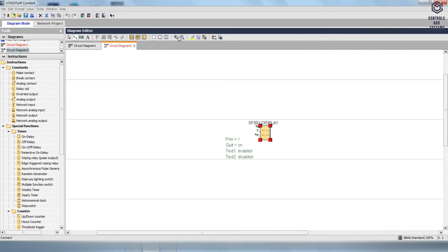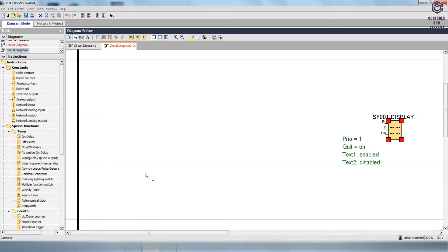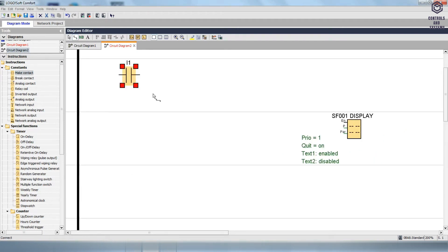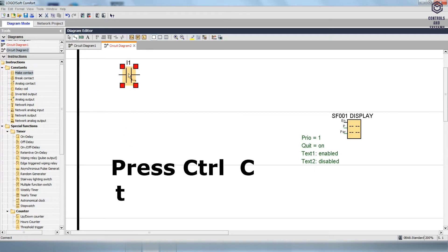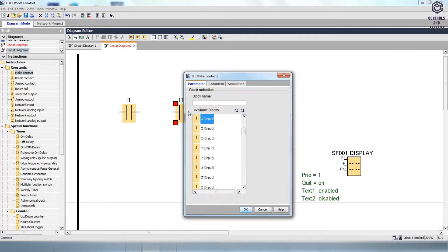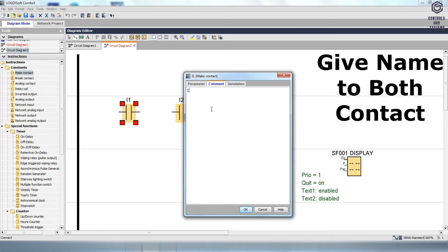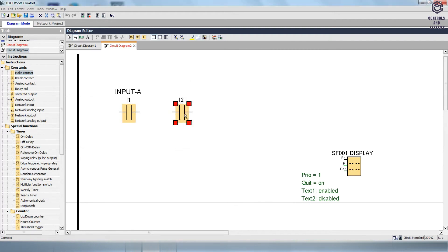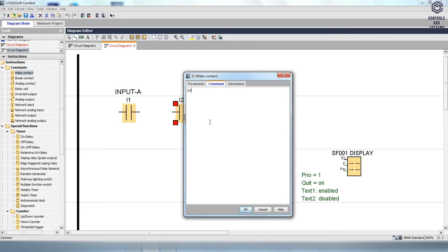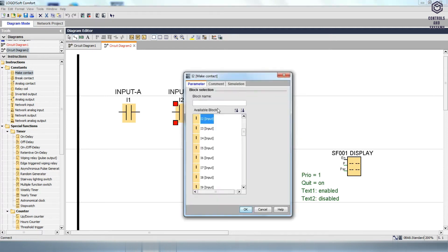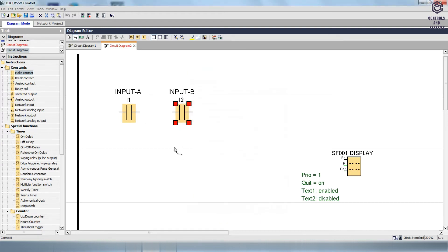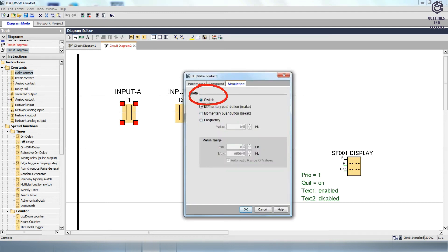OR gate: add the Message Text block from the Miscellaneous folder. To add the input block, drag and drop the Make Contact from Constants and consider it a NO contact. Press Ctrl+C to copy the input block and Ctrl+V to paste another input block. Double-click the second input contact, go to the parameter, change I1 to I2, and click OK. Double-click the I1 contact, go to the comment, give the name as Input A, and click OK. Double-click the I2 contact, go to the comment, give the name as Input B, and click OK. Double-click the I2 contact, go to the Simulation, select the Mode and Switch Type, then click OK. Repeat the same procedure for the I1 contact.